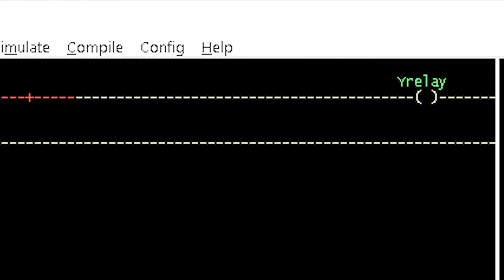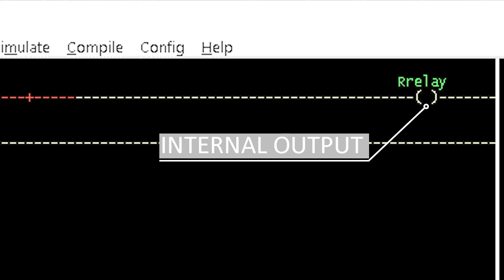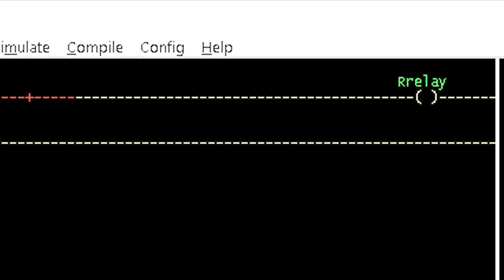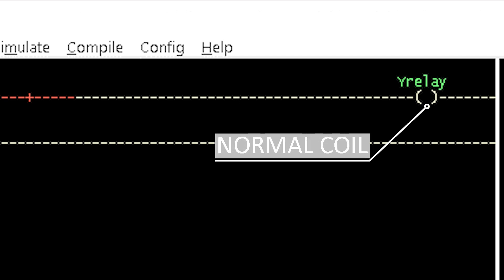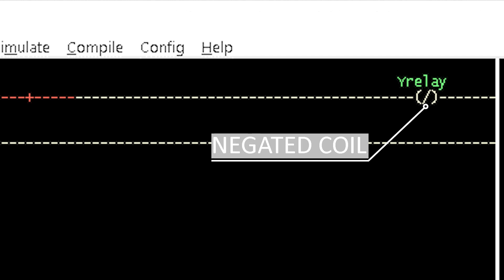Now let's consider the coil. A coil or relay outputs the result of a ladder logic to an external device such as LEDs and buzzers, or an internal relay which could further be used as input to a ladder logic. A coil must be the rightmost instruction in a row. A coil that outputs the exact signal of a ladder logic, either true or false, is called a normal coil, while the one that reverses the logic signal — true becomes false and false becomes true — is called a negated coil.